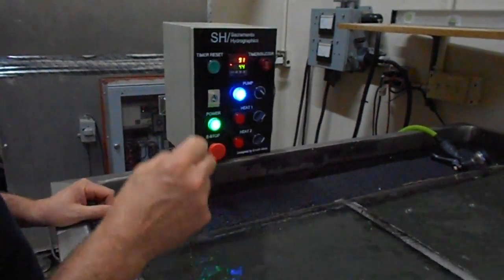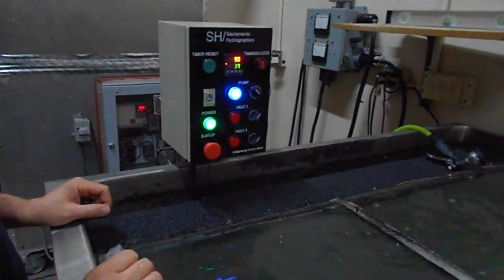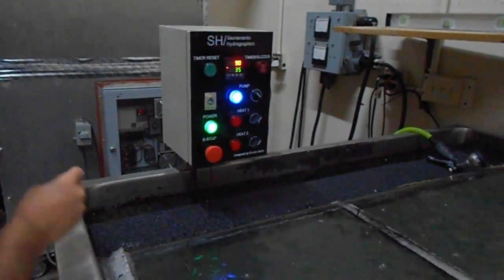This will actually turn off at 91 degrees. As soon as it sees a hint of 91 degrees, the heaters will turn off. As it drops down to 89, the heaters will turn on. I'll demonstrate that real quick here.